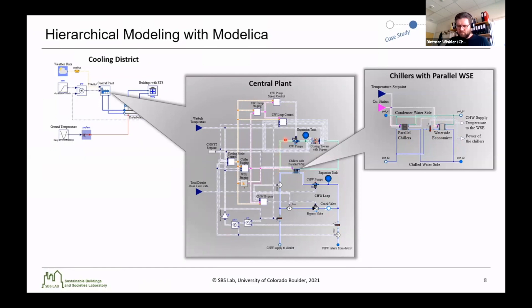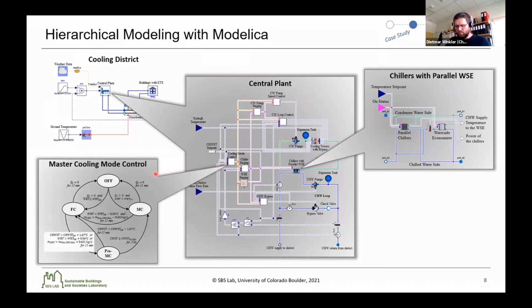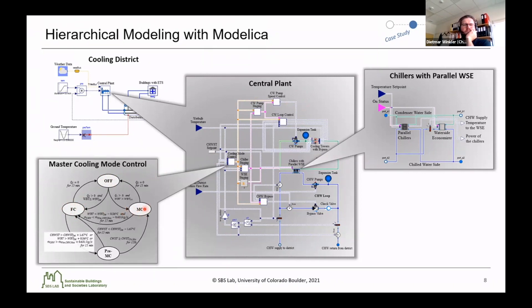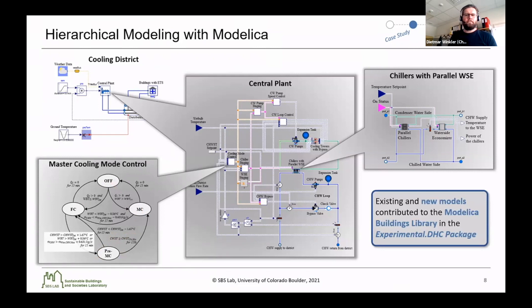Also in the central plant, there are a variety of control blocks that reflect the real hierarchical control of this plant. As one example, looking at the cooling mode control — the top master level control — for this plant, you can operate in a variety of different states: off, free cooling mode when the economizer is running, mechanical cooling mode when the chillers are running, and a pre-mechanical cooling mode to protect the chillers. All these models use some existing models from the Modelica Buildings Library, and we also added new models to the Buildings Library, particularly in the experimental DHC package, to allow others to do case studies for district cooling systems. In the Buildings Library, we have released generic plants and district configurations to study a variety of different systems.